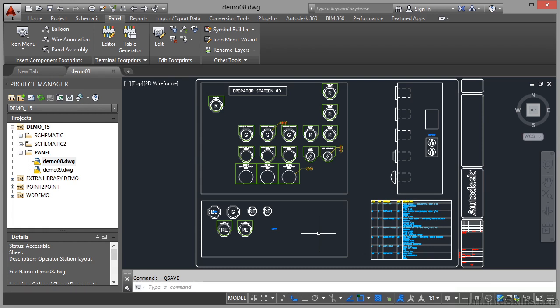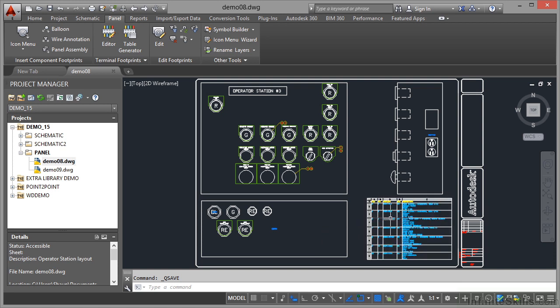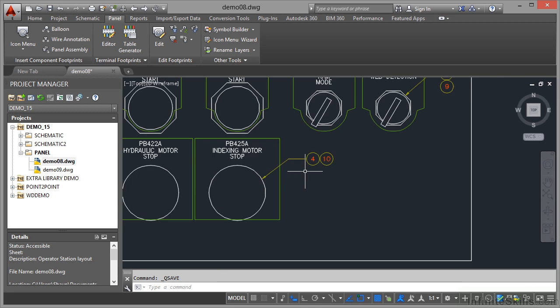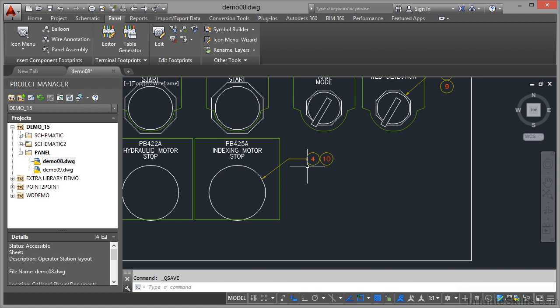It's standard procedure on a panel drawing to add balloons to your components so your footprints have little balloons coming off of them, referring to the table on the drawing. Let's look at some existing balloons. If I zoom in, you can see numbers 4 and 10. That indexing motor stop button has the numbers 4 and 10 because they're the panel footprints that make up that particular indexing motor stop button.